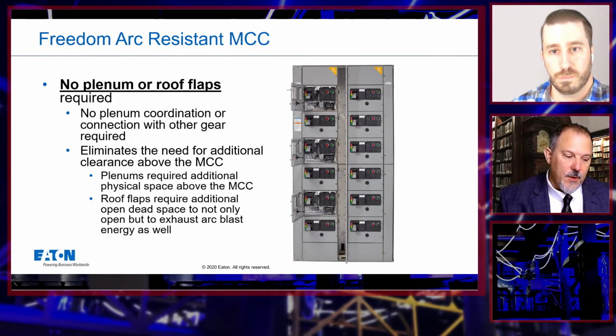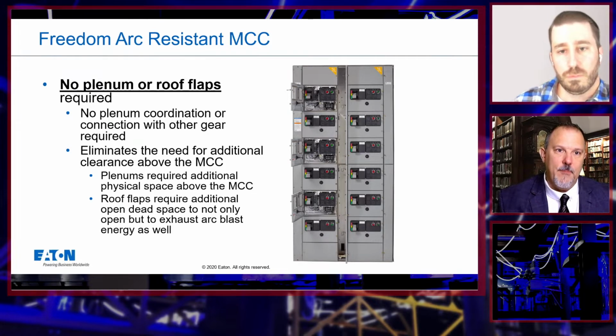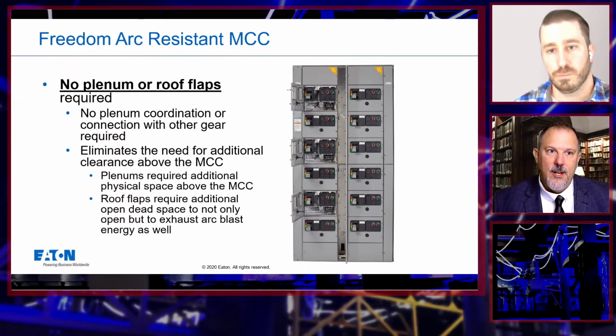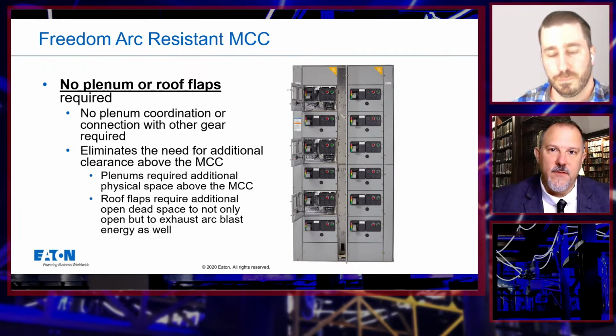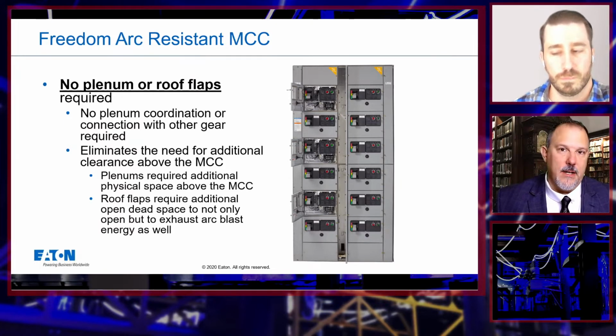Which is the point that was made to me earlier when we're doing these tests in a lab, not in equipment. Based upon the construction of equipment, I could get significantly lower incident energy for the electrical worker. I'll calculate a number, but it will be significantly lower because of the construction of the equipment, and it won't sustain itself.